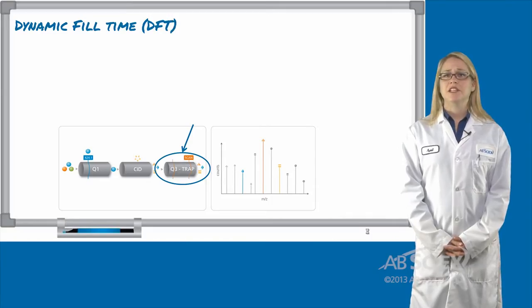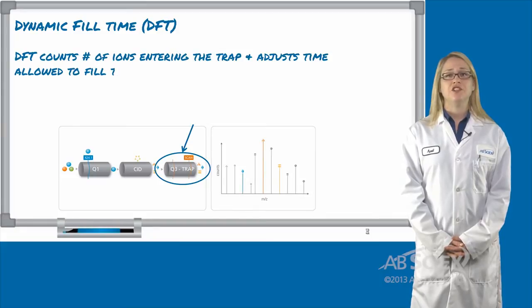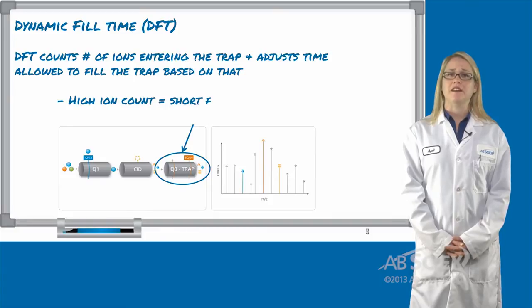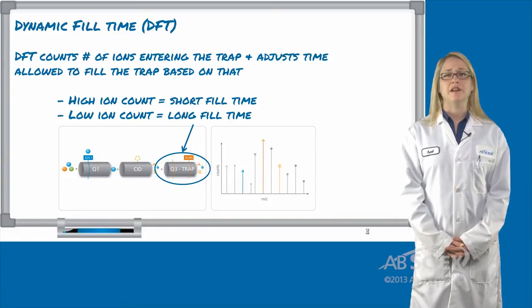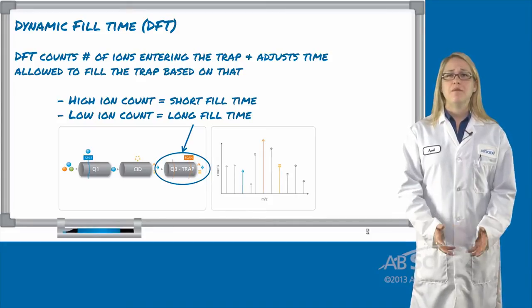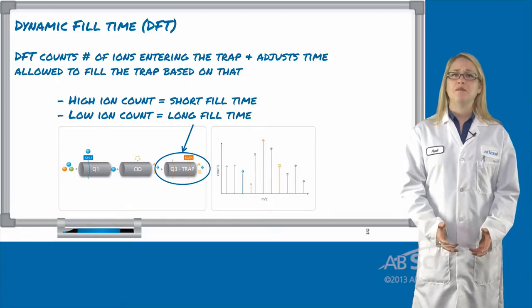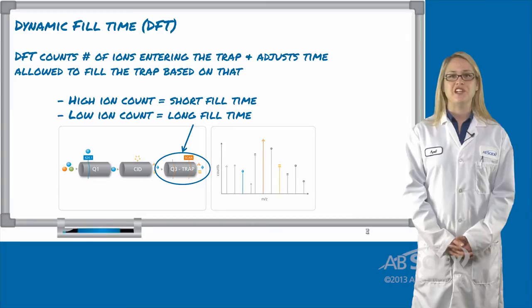The dynamic fill time is the time allowed for the trap to fill with ions before they are scanned out for detection. If there is a high ion count, a shorter fill time is activated, while if there is a low ion count, a longer fill time is activated. DFT should always be activated in an EPI experiment. Dynamic fill time is data acquisition optimization on the fly and will ensure the best quality spectra for your experiments.